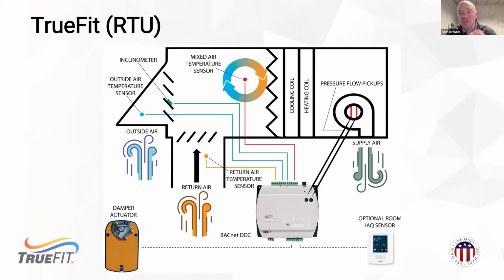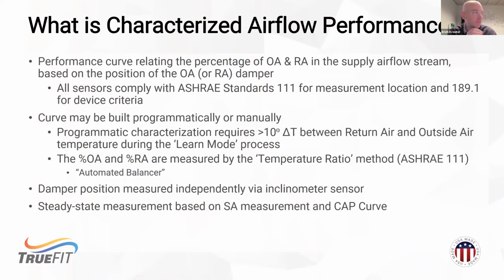The new term here, a new component for most people, is something we call an inclinometer. This is a tilt sensor commonly found, like, in your car or a piece of agricultural equipment, but this provides us a repeatable position of where that mixed air damper assembly is. And once these components are installed, we have a measurement method called characterized airflow performance.